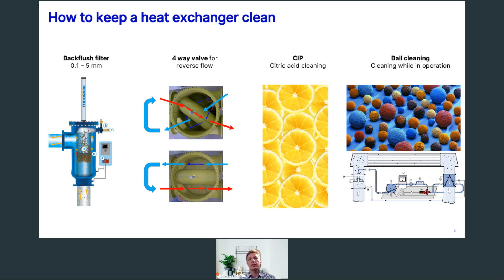The fourth option is the ball cleaning system, where you have a shell and tube. Then you can have small rubber balls being flushed through the tubes while it is in operation. So if you have a heat pump system that you need to operate 24/7, this is the best solution, because while it is in operation, you send these rubber balls through the tubes, which clean the tubes while you are still producing heat. So you don't interrupt the production of heat, which you will have to do if you are CIP cleaning a heat exchanger.